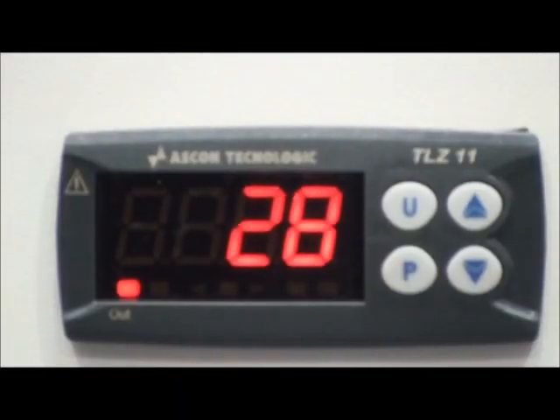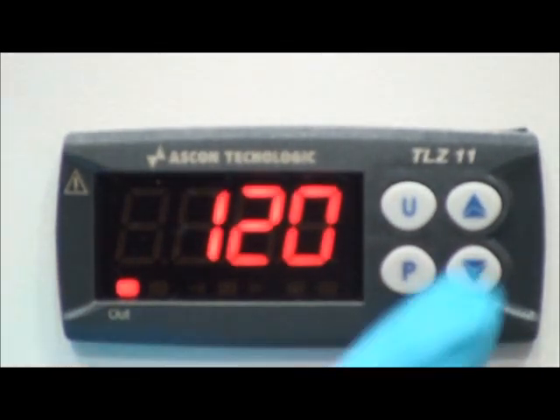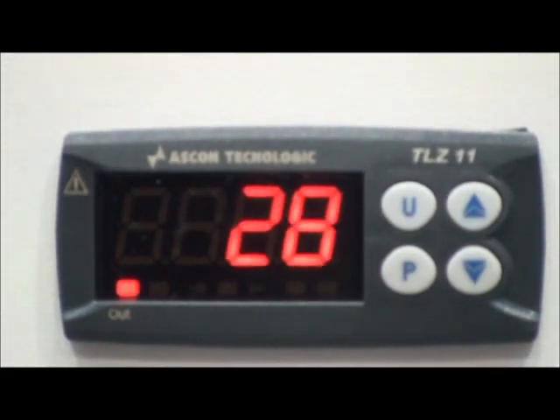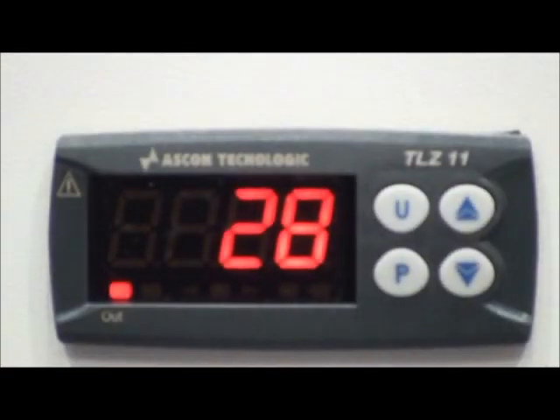Next we're going to look at the heater control. This is unique on the Fumecare cabinet, which allows you to set the hot plate at your desired temperature. To access the set point, you press the P key, and that displays the set point at 120. To adjust upwards or downwards, you press the up and down keys and then P to accept. At the moment it's displaying the temperature inside the chamber. The set point is a user operation.